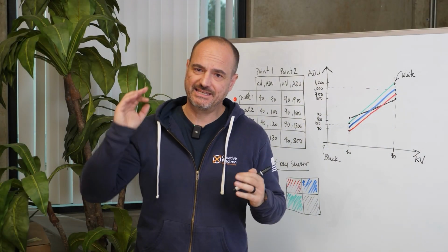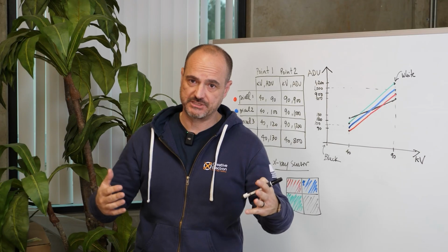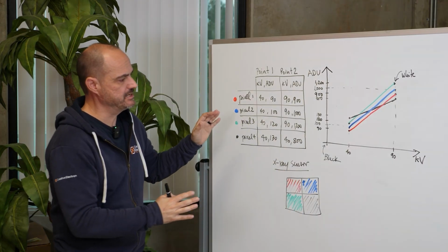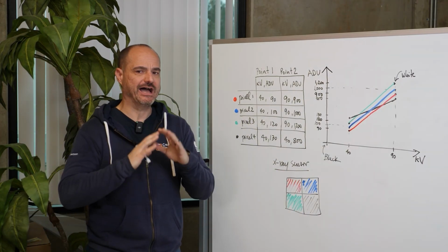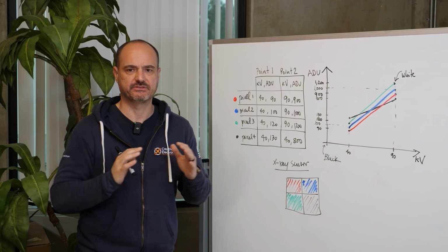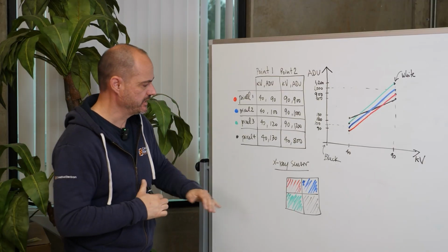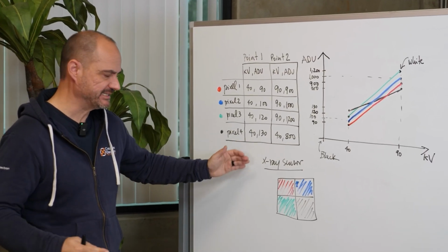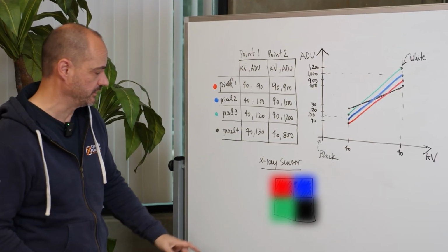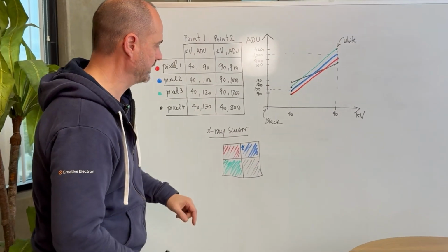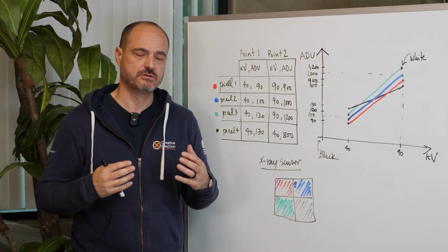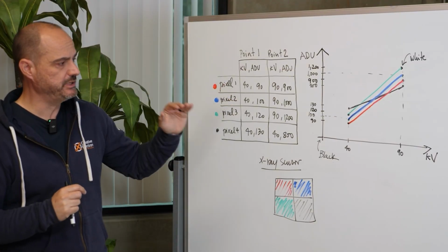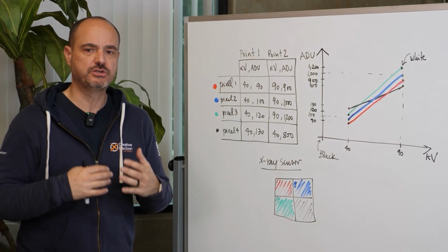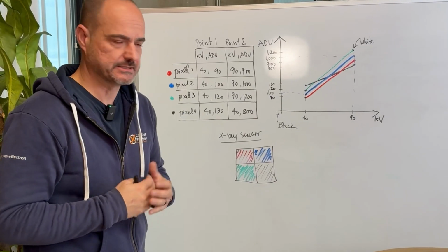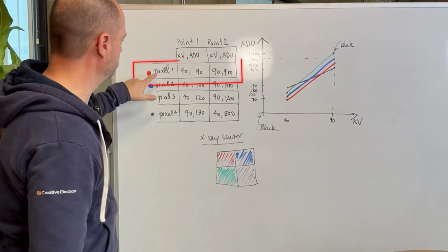So calibration is an interesting topic when we talk about X-ray inspection and X-ray machines. What I did here is to give you guys an idea of how and why we calibrate the sensors on our X-ray machines. So let's start with a very simplistic X-ray sensor with 4 pixels only. Pixels 1, 2, 3, and 4. And what's interesting to observe is that each pixel has a different response to the radiation that we put on it. So for example, let's go to pixel 1.